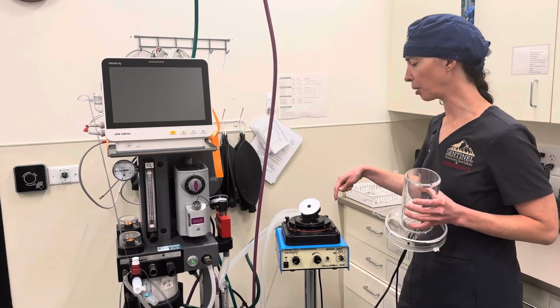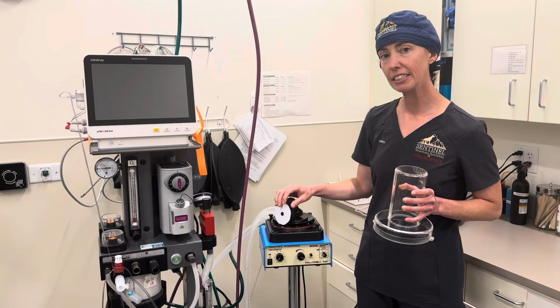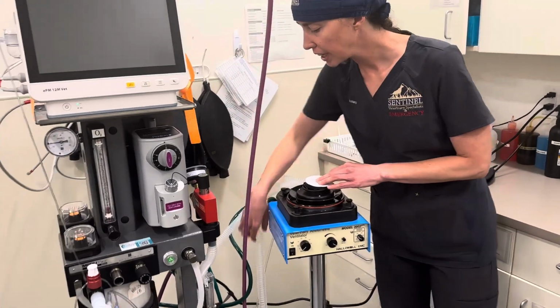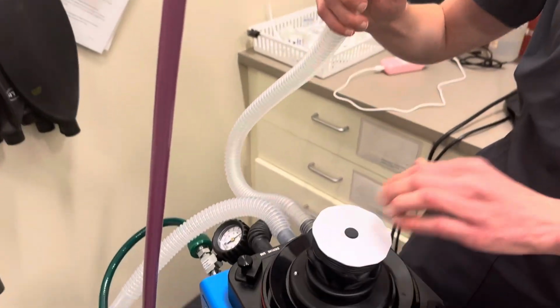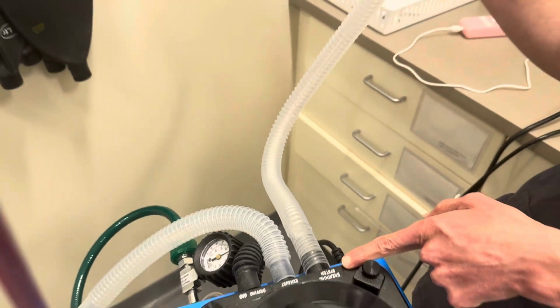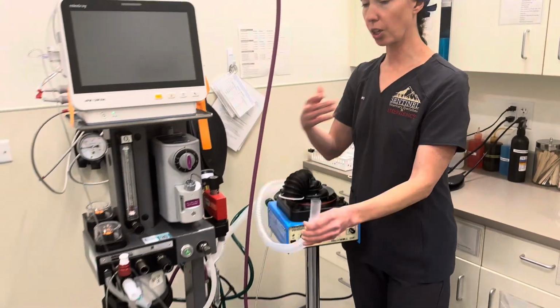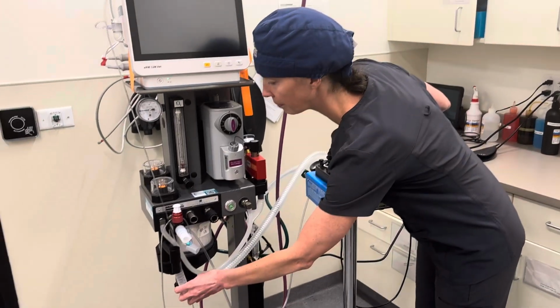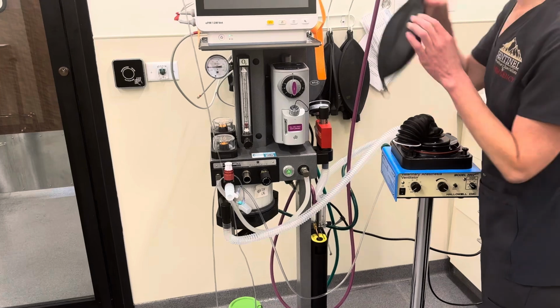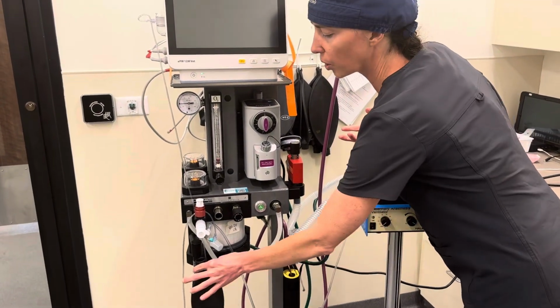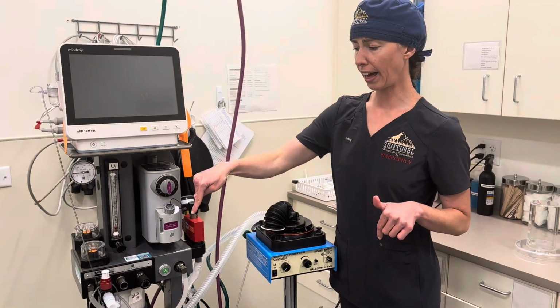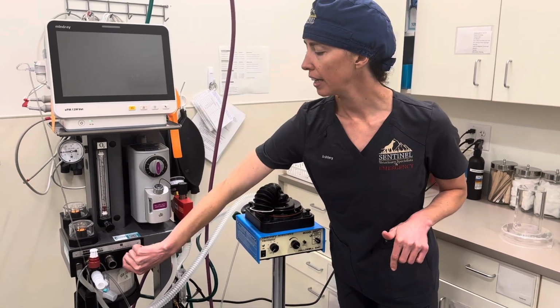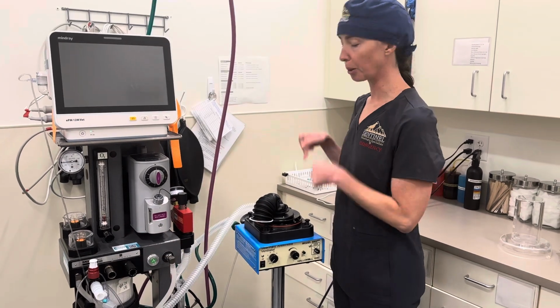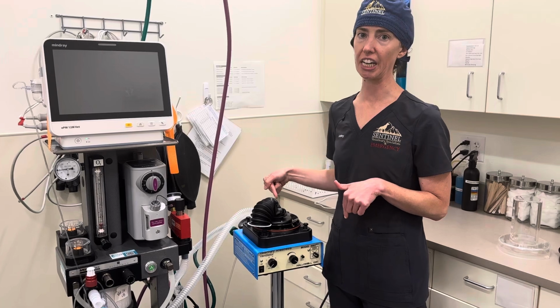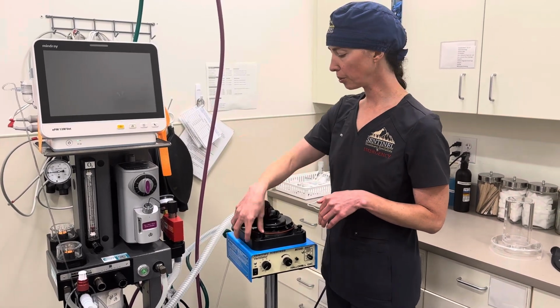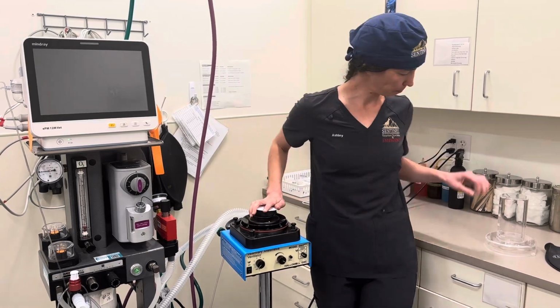And then a couple other things on the back of the machine, you'll see a hose for the breathing system. That hose is this guy right here, and there's the breathing system tag right there. You take this and hook it up to exactly what it says to do: hook it up to the breathing system. We're going to put it right here, which is where your reservoir bag, also known as a rebreathing bag, would have been. Once you hook that up, you can actually close your pop-off valve. The reason you can close it is because there's a built-in pop-off valve on the back of this machine, and it will pop off when it needs to, so you don't over-pressurize the circuit.